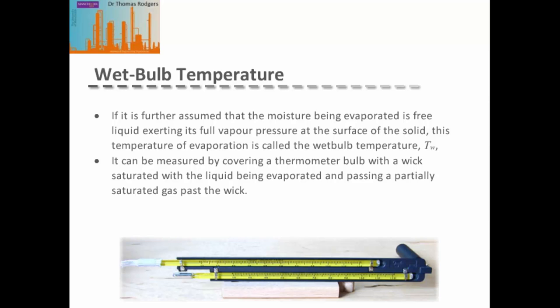The wet bulb temperature can be measured by covering a thermometer bulb in a wick saturated with the liquid being evaporated. In the typical setup, the dry bulb thermometer measures the gas temperature, while the wet bulb thermometer — identical but with a moisture-saturated wick on the bulb — gives the wet bulb temperature.